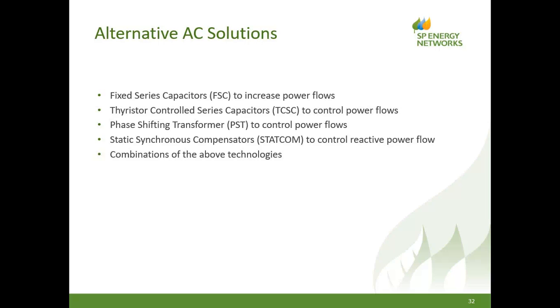Or we could have put in static synchronous compensators, STATCOMs, to control reactive power flow on the island grid and on the mainland grid. And essentially what we've done with MVDC is a combination of a phase shifting transformer and two STATCOMs, if you like, which would be the competing AC solution to an MVDC technology. So MVDC is a good solution for this particular application. It's a good demonstration of the use of DC technology in the UK distribution networks. But we are conscious that there are other AC solutions which could be available. I thank you for your time.